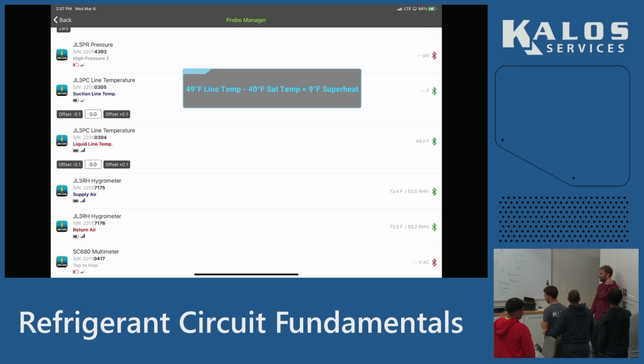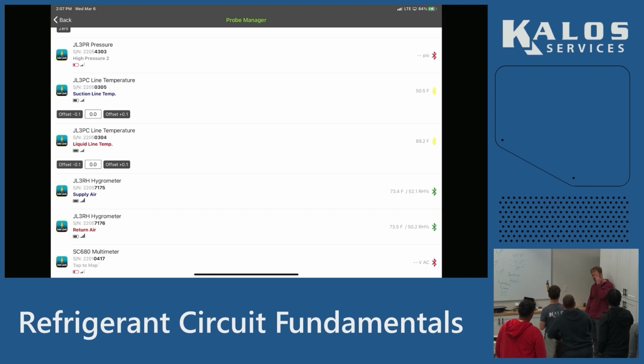It's 49, yeah. All right, what's our superheat? 9. 9. Very efficient coil. It's doing its job. We have come above the mixture state, 9 degrees. We know we're 100% vapor. You go above saturation, you're vapor. You go below saturation, you're liquid.